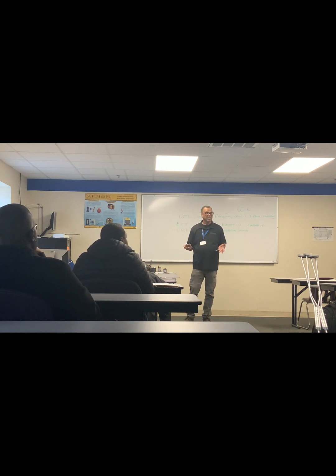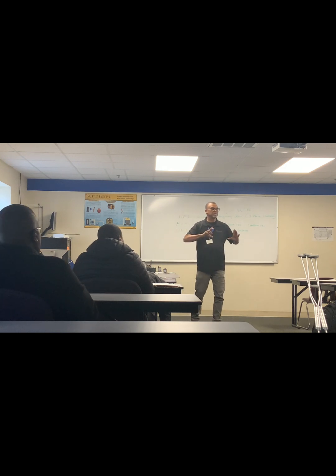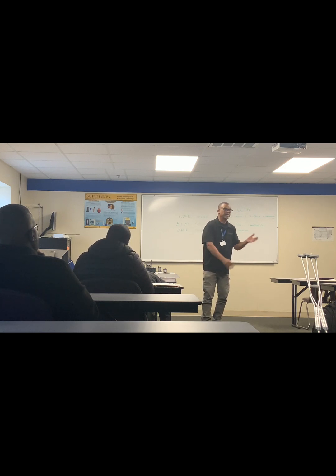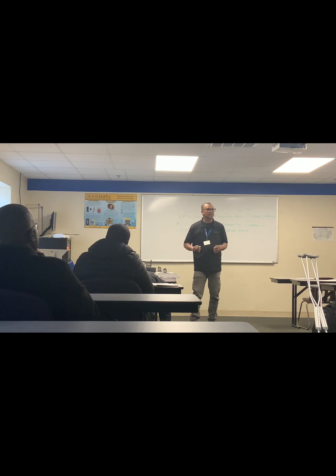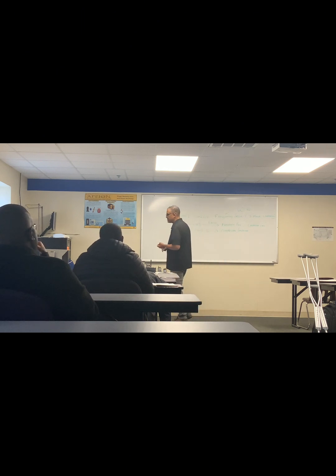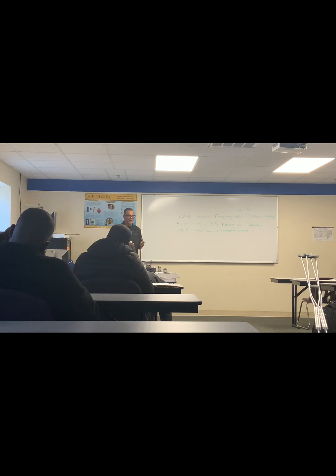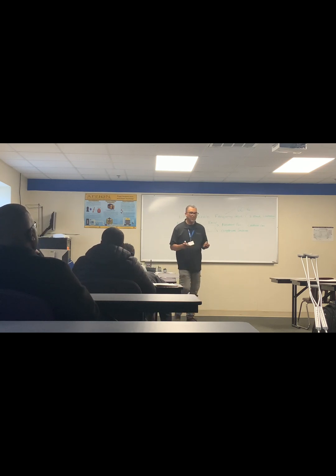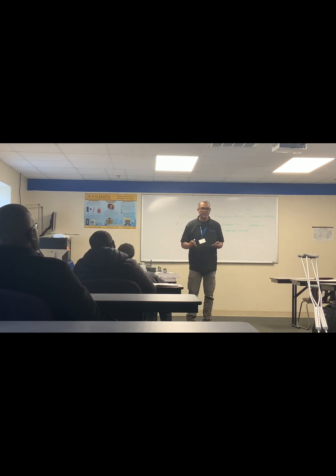You said the smallest going what now? The smallest pulley goes on the motor. Okay. The larger one is on the circulation distribution wheel that's pushing the big blades that push the air through the duct. So belts have to be a certain size, pulleys have to be a certain size, and then it's certain math that you get a ratio of how many turns you get out of the smaller motor compared to how many rotations come from the big one, and they call that a ratio.